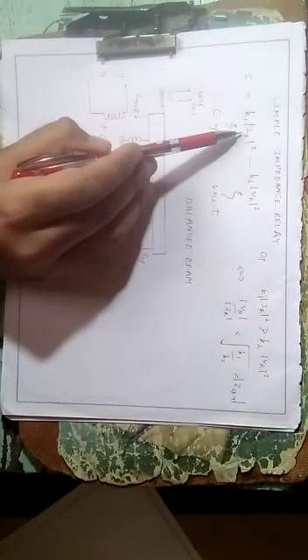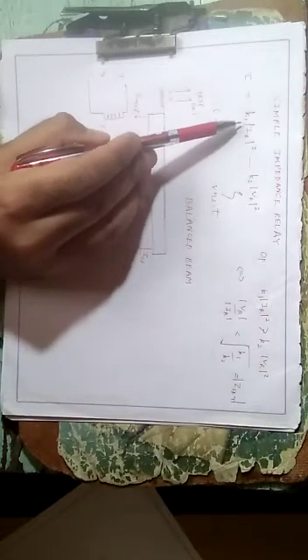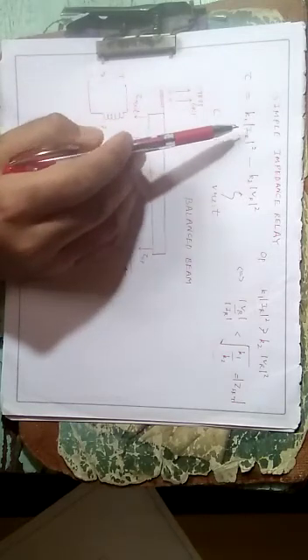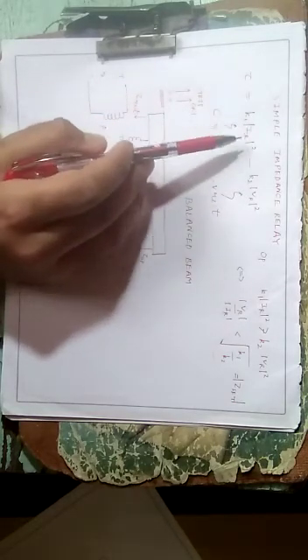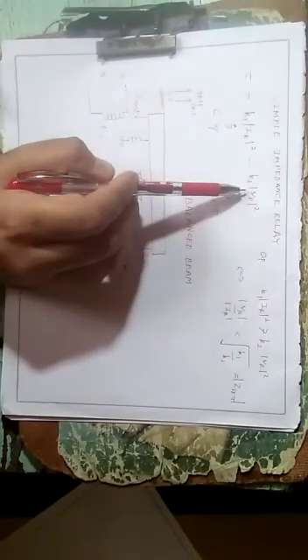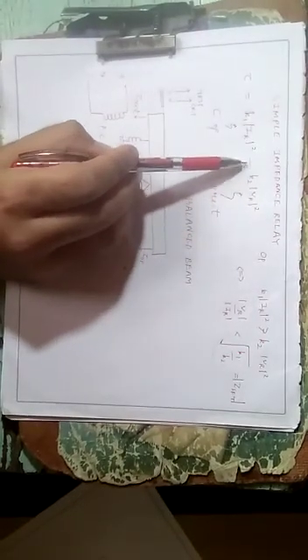The larger the value of current, the higher is the possibility that the torque becomes positive, and hence the higher the probability that the relay will operate. It will pick up. The larger the value of voltage, the larger is the possibility that because of this negative sign the torque becomes negative or the relay will restrain.